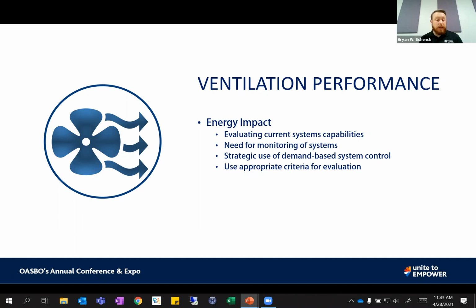Demand-based ventilation is something that's very often used in our facilities, if we have the ability to evaluate CO2 based on a space, bringing in more ventilation air the more occupied that facility is. With the pandemic, a lot of those have been disabled, and we're starting to just bring in as much outdoor air as we can. That's very much an energy thing - we've done that, and those systems are in place to not overconsume energy by bringing in more outdoor air and having to heat or cool it.